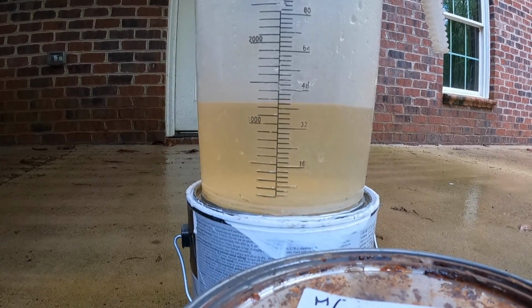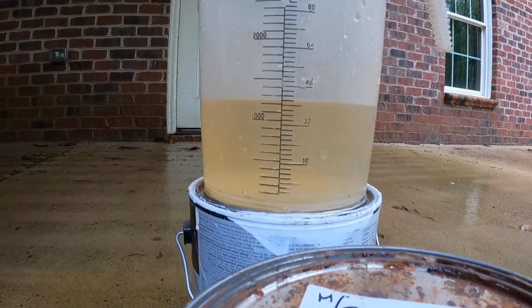Looks like we put out about 43 ounces in 20 seconds. So I can't believe it. Looks like we actually did see a gallons per minute increase, and that was simply by shortening the suction line. We do know the pump's primed. It's spraying out a really good pattern.